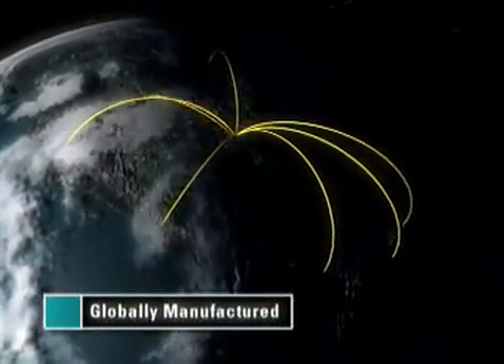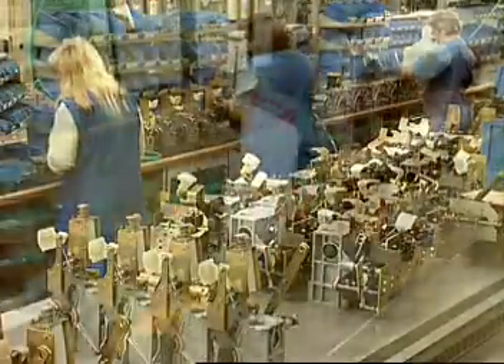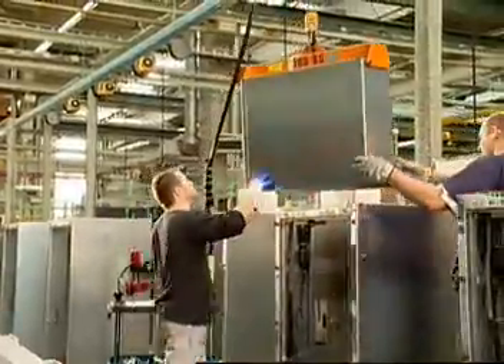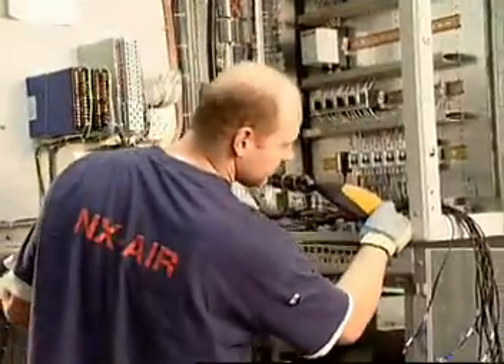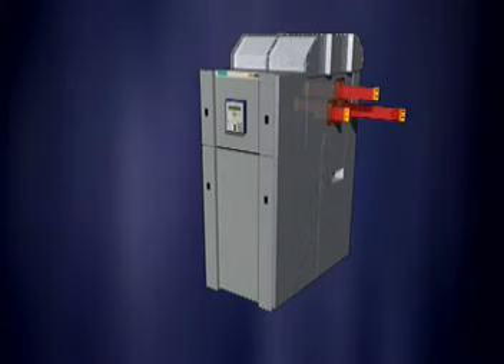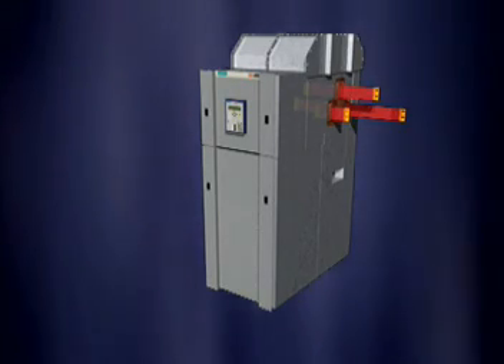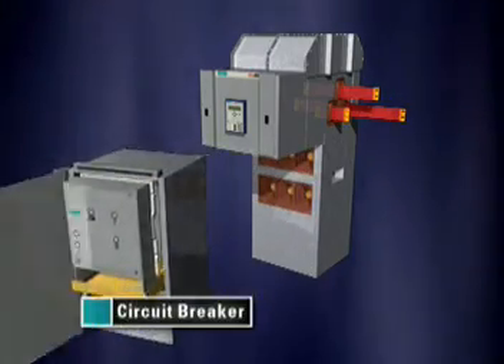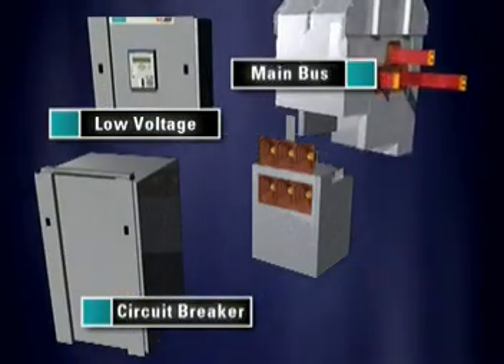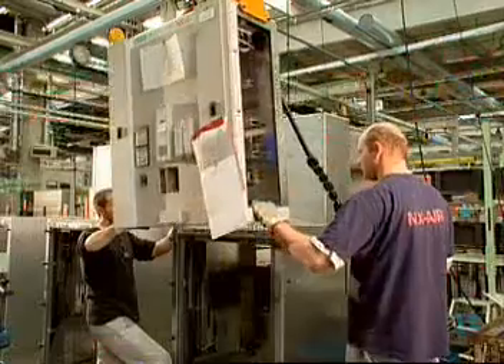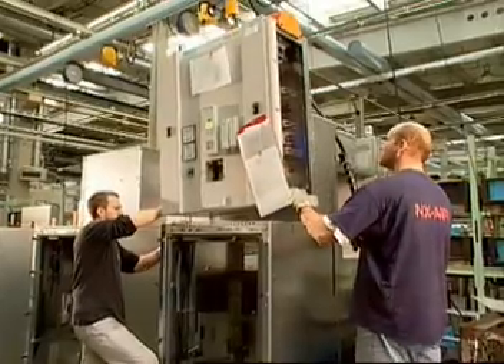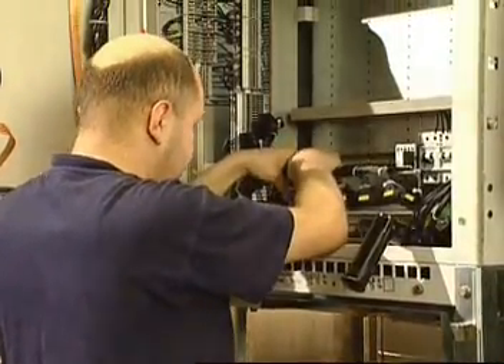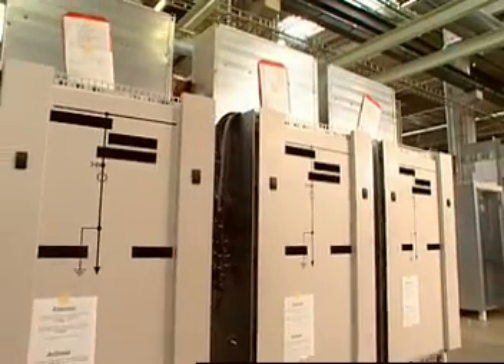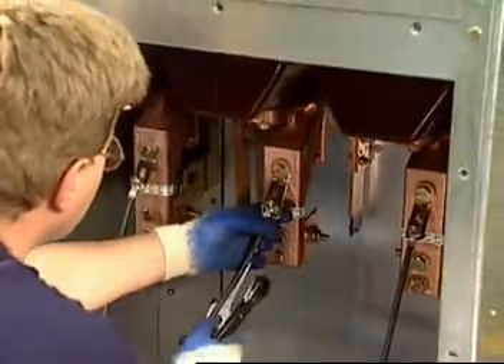Speed of manufacturing and delivery is crucial in the global marketplace. To meet these demands, Siemens adopted a modular design for the NXAirP. By globally manufacturing the NXAirP and modular components, we can deliver our orders more efficiently. In fact, the NXAirP can be delivered as quickly as 11 weeks from your order date. A section of Siemens NXAirP switchgear is made up of 4 modules or compartments: a circuit breaker compartment, a low voltage compartment, a main bus compartment, and a cable compartment. Its modularity also allows for easy installation of the low voltage compartment in the field. This is particularly beneficial on fast-track jobs where the primary portion of the switchgear needs to be installed ahead of the relaying, metering, and control.